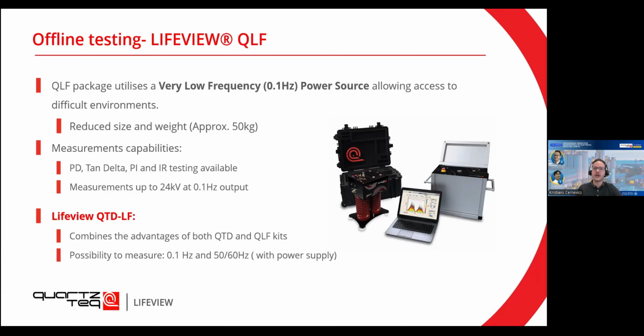And then there's the combination of both that we call the QTD LF, which combines the advantages of both the QTD and the QLF. The possibility is to measure with this low frequency source at 0.1 hertz, and also, if you have an external power supply, you can measure at 50 or 60 hertz.